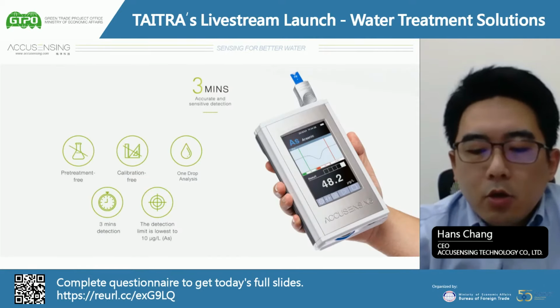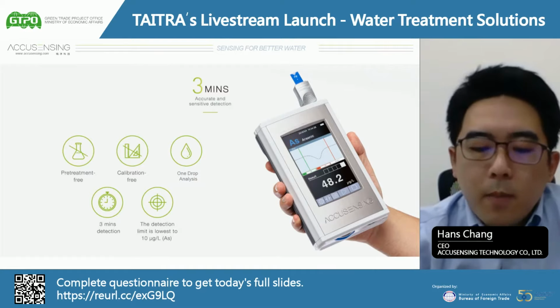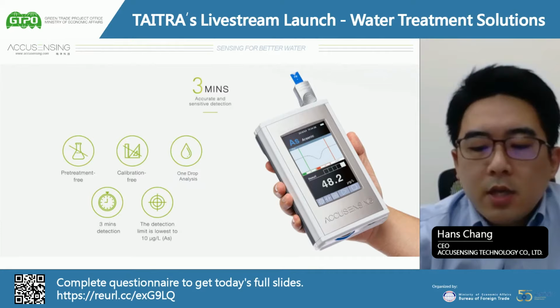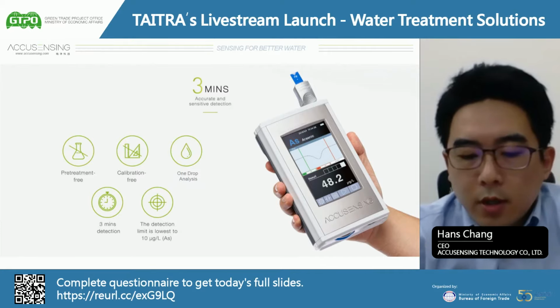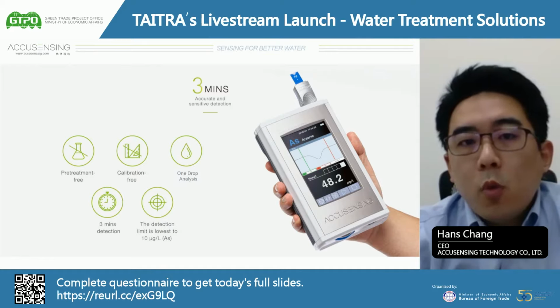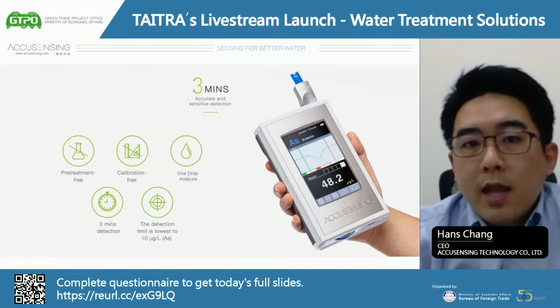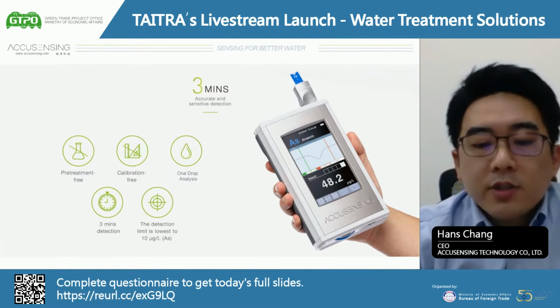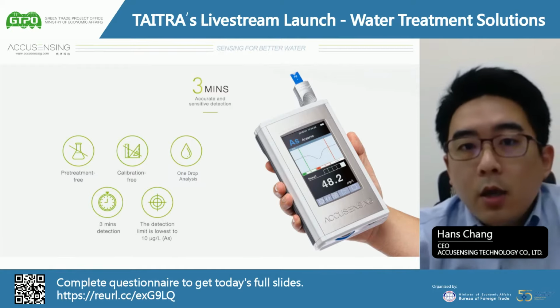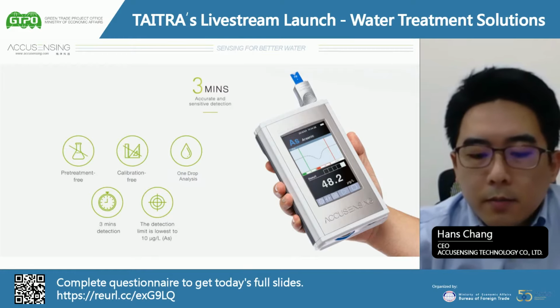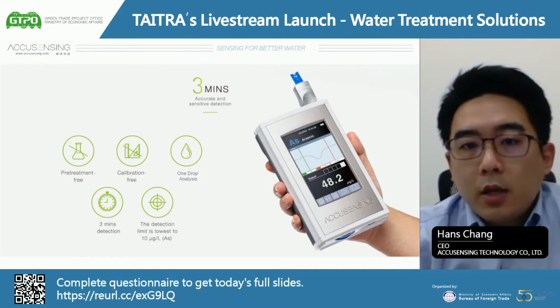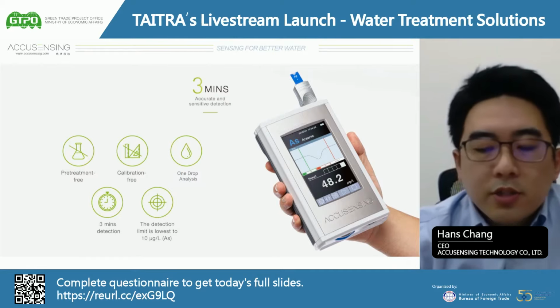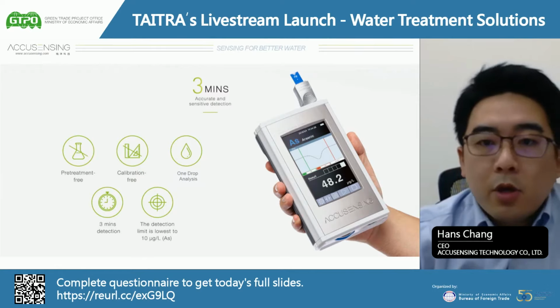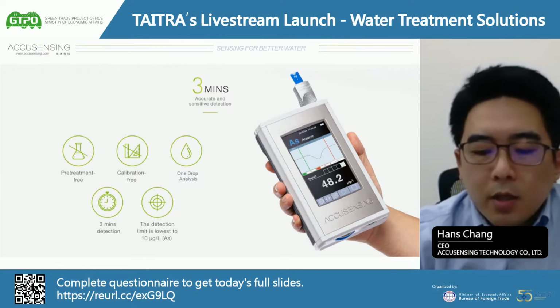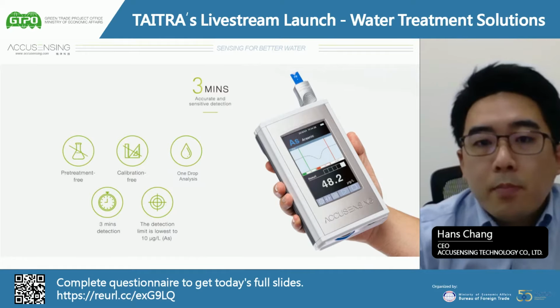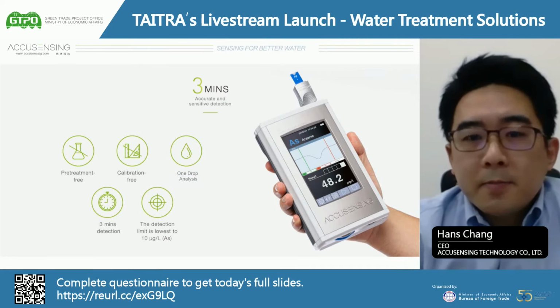Here we present the features and advantages of MAS. First, 3 minutes detection time without pretreatment and calibration. In Taiwan, we have to wait 2 or 3 weeks for a laboratory report. Second, lowest volume needed. Only 1 drop of water is enough to be detected. Third, MAS will give you a digital reading on the screen, so even users who don't understand the complicated chemical graph can use it. Fourth, the limit of detection reaches 10 micrograms per liter, ppb level. Next, please.